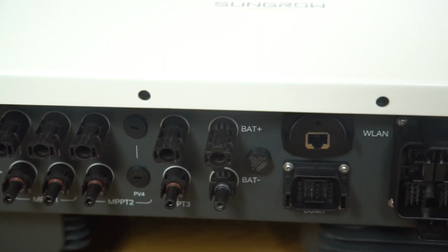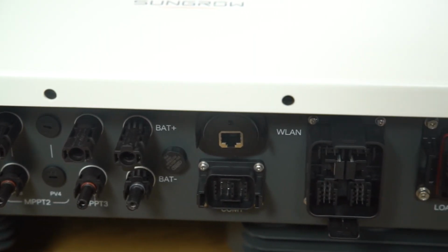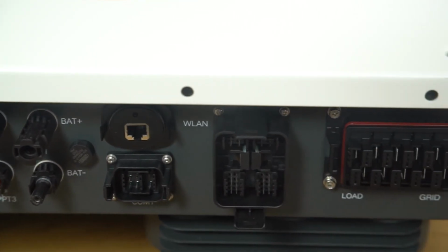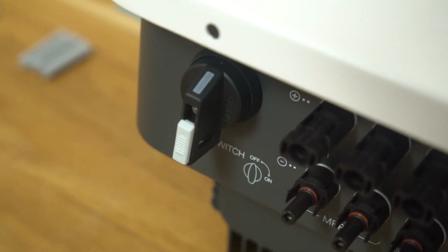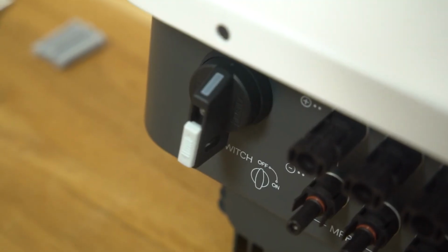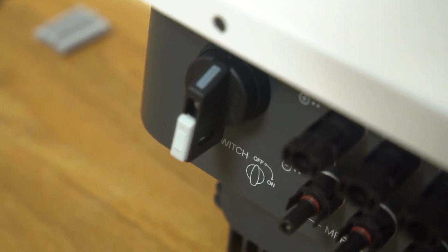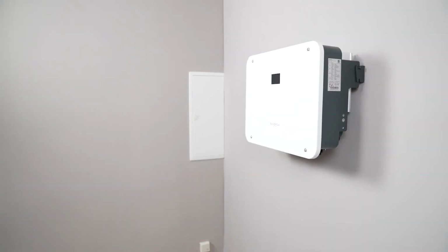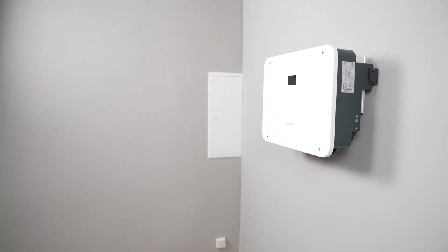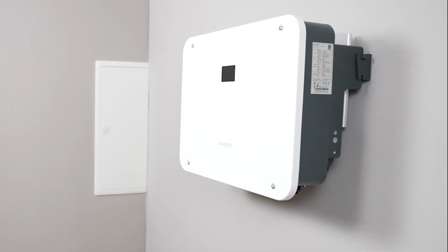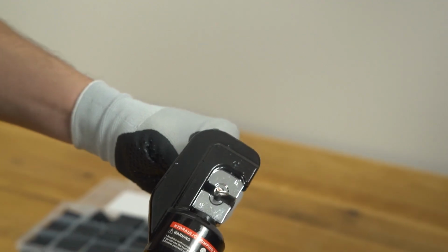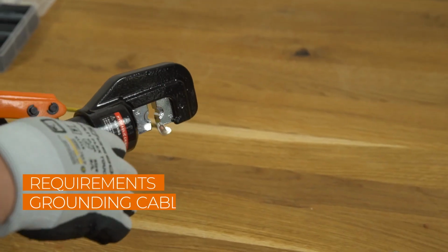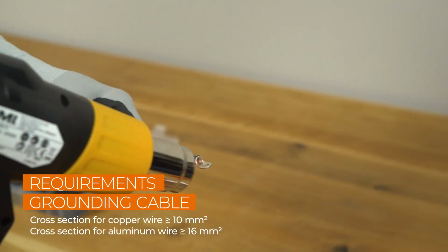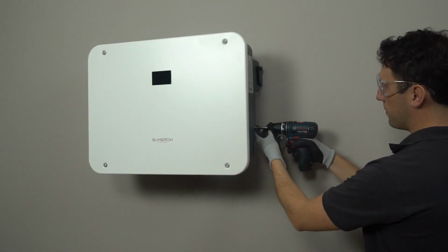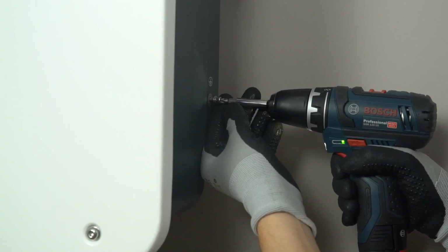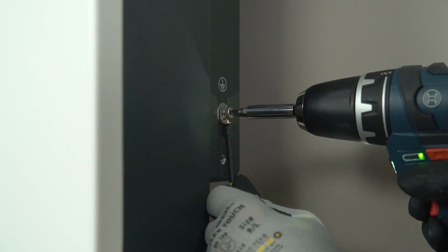Keep both the AC and DC switches disconnected to avoid live line operation. Set the DC switch on the left side of the inverter from on to off. There are two PE connections, one on the left side and another one on the right side of the inverter. At least one of them must be connected to the general grounding of the house. Crimp the grounding cable, remove the screw on the grounding terminal and fasten the cable with a screwdriver.